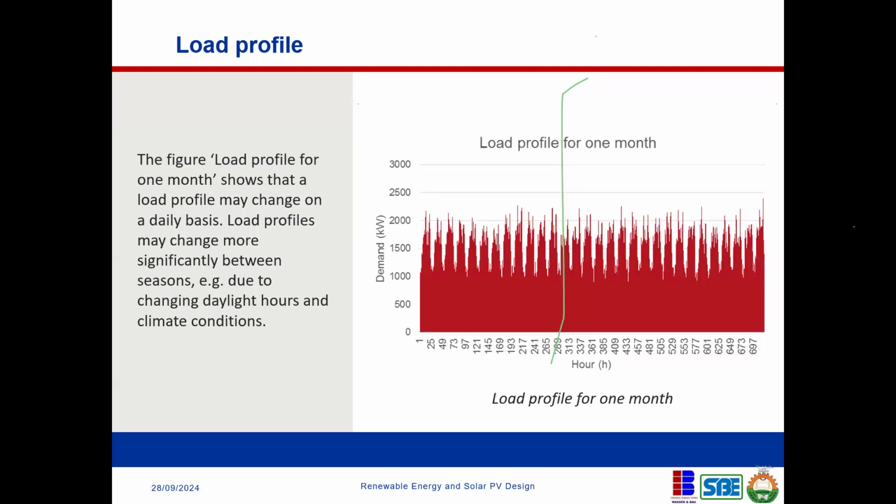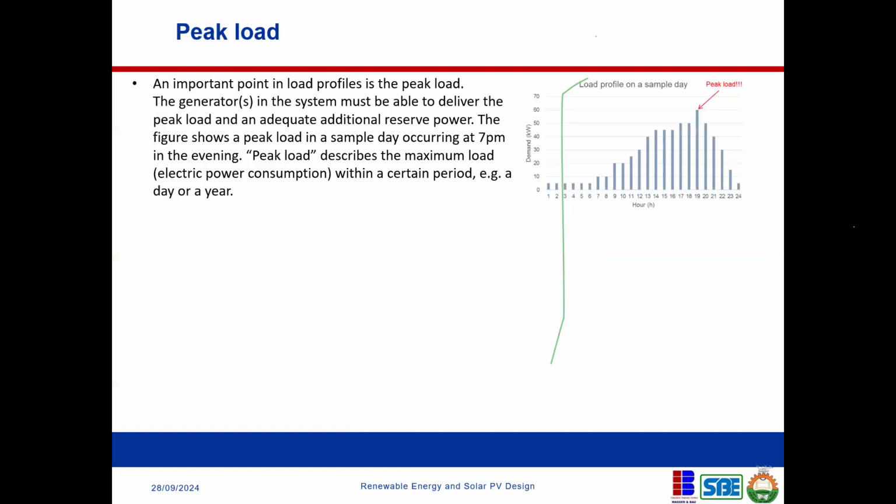So this is what a load profile looks like over a month. There are projects that, if we want to embark on them, because we are not sure of their load demand, we have to install meters on site and monitor their energy profile over one month. In fact, sometimes we'll do that depending on the size of the project. If it's a city project, sometimes we monitor the load profile for over 6 months and we extrapolate for the remaining 6 months, because we may not have the patience to wait for a complete year to have a complete year load profile. We do it for a month, extrapolate the rest of the months, and use that for our assessment. So like I said, this is what a peak demand looks like. This is what a peak load looks like.